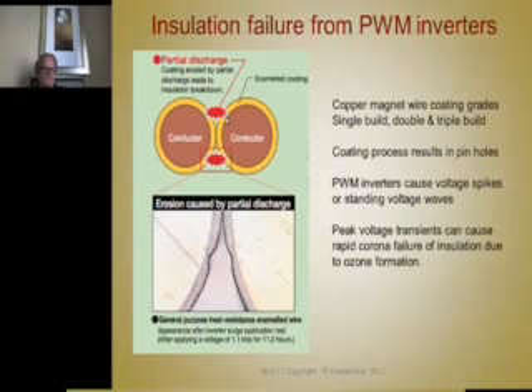The first turns of the first coils in series for the phase circuits are subjected to this big standing voltage wave that's transmitted through the lead wires from the PWM inverter. So it causes a big potential across any leakage paths there. And what that does is cause ozone. And ozone is like acid, and the ozone that's created there from the surrounding air causes a very rapid breakdown of this insulation, so you get a turn-to-turn short from that.